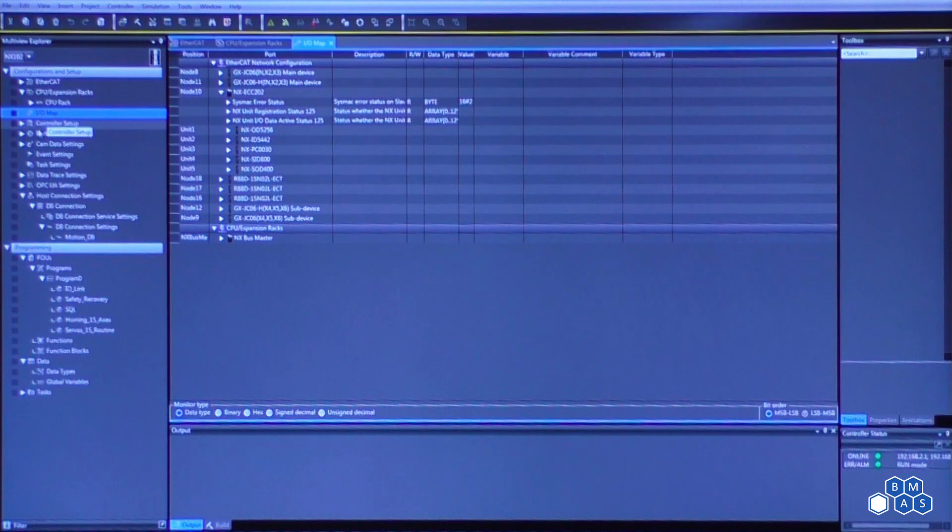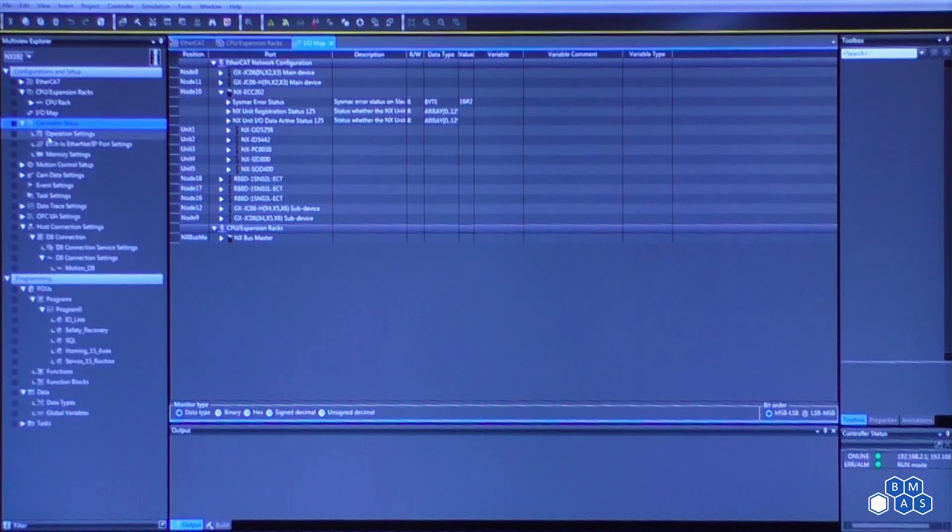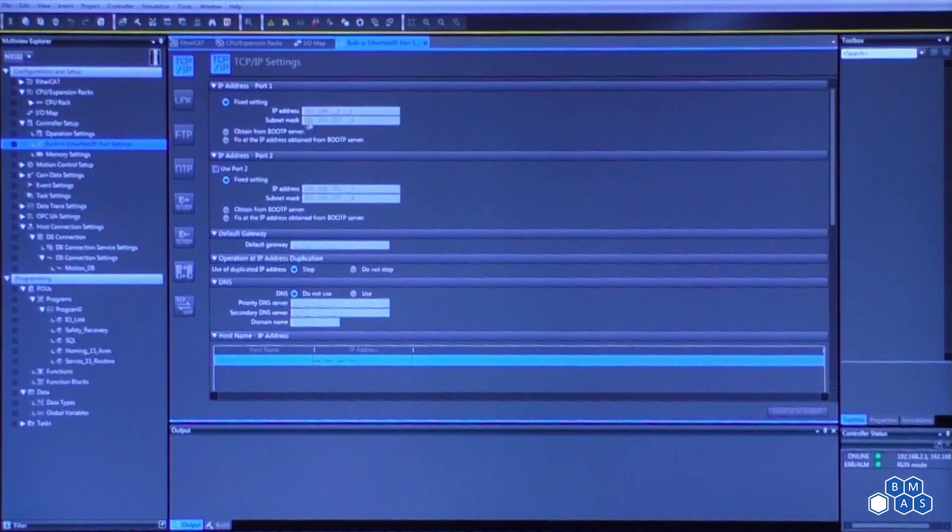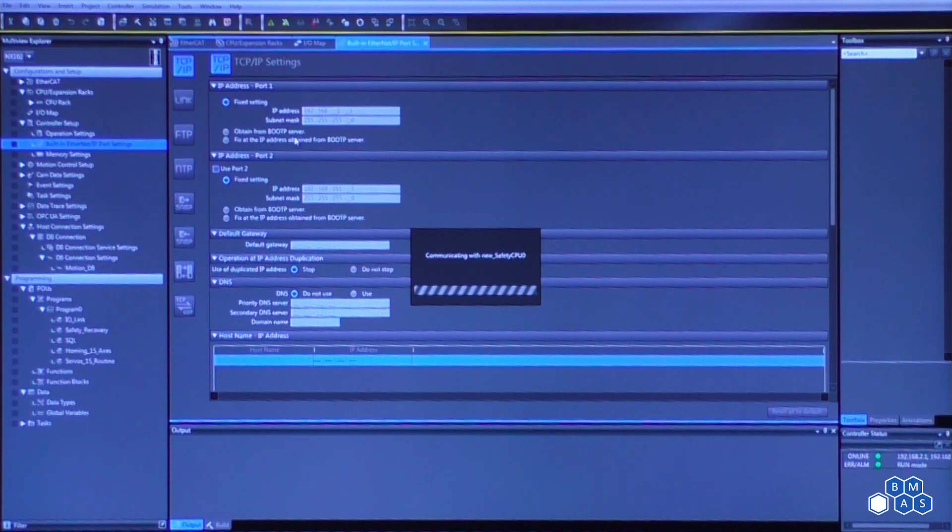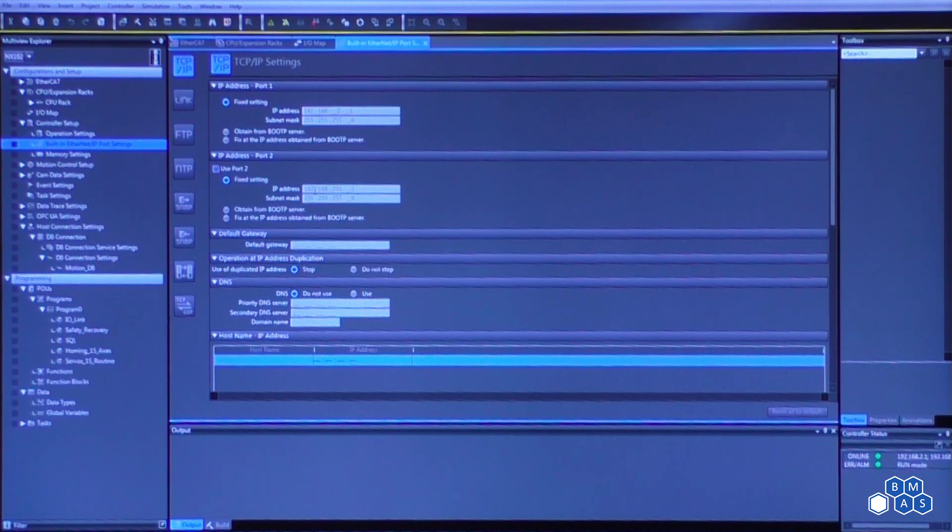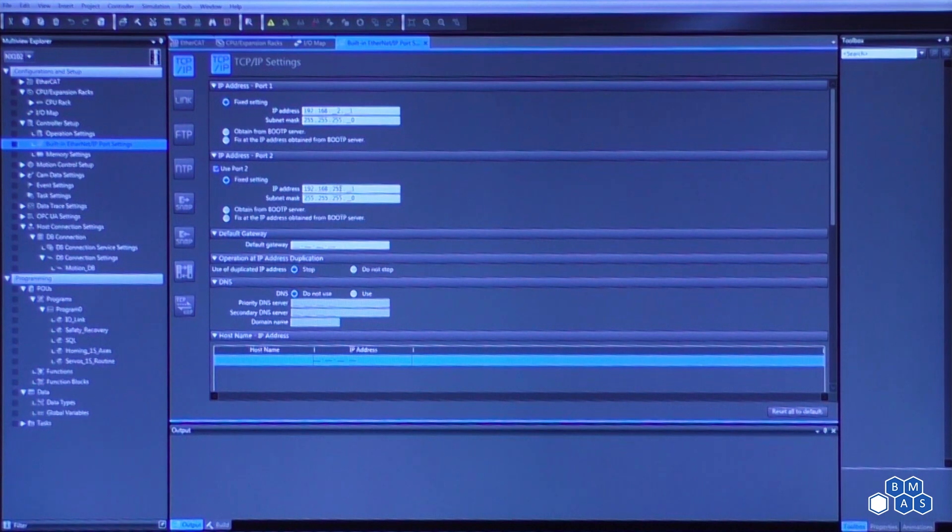After we've completed that, we can get down to whatever we want to set our IP address to. Notice that as we mentioned in a previous video, there are the two ports on the NX102 series PLC. So as we see here, there are port one and port two settings. So both of these must reside on a separate subnet. You'll notice the 192.168.2.1 versus the 251.1. They must reside on separate networks.